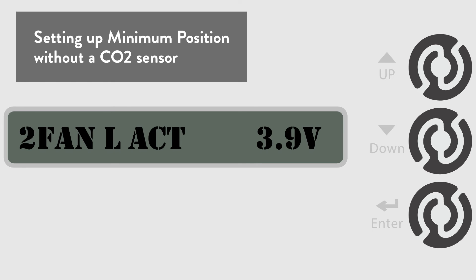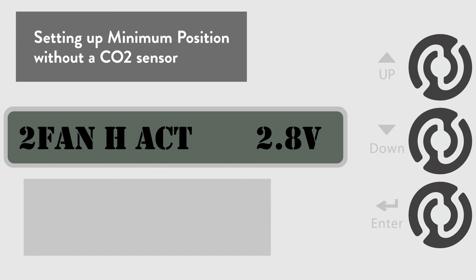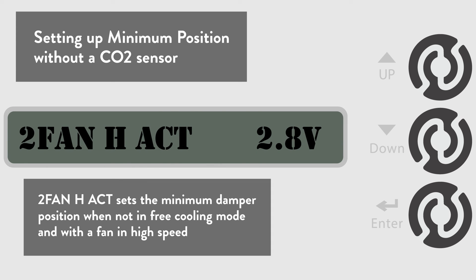Now go to the 2-fan H-ACT menu. This will set the economizer actuator voltage or the damper position for allowing minimum position outside air intake when the fan is in high speed. The default is 2.8 volts, but for this example we are going to change it to 3.0 volts.